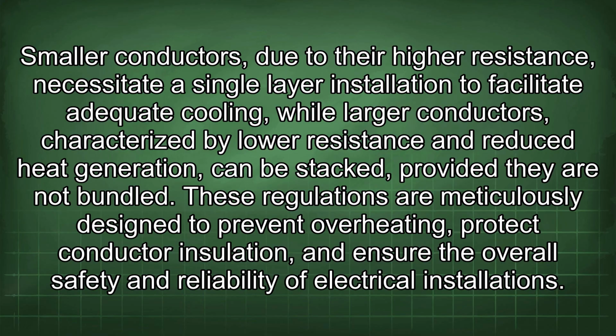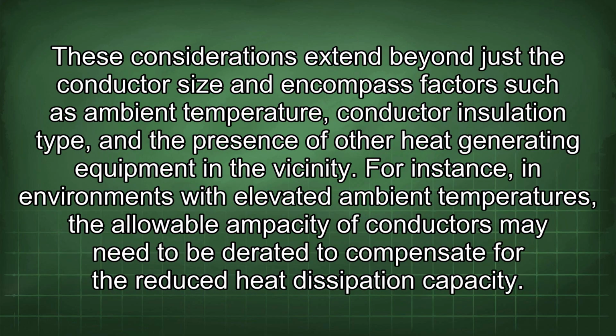These regulations are meticulously designed to prevent overheating, protect conductor insulation, and ensure the overall safety and reliability of electrical installations. These considerations extend beyond just the conductor size and encompass factors such as ambient temperature, conductor insulation type, and the presence of other heat-generating equipment in the vicinity. For instance, in environments with elevated ambient temperatures, the allowable ampacity of conductors may need to be derated to compensate for the reduced heat dissipation capacity.